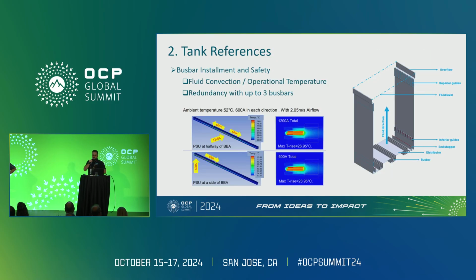Here you have more examples, for example the fluid convection, how the temperatures are being studied for the busbars. You'll see later on with Kevin when he speaks and touches on the more specific power side of things. But the advantage of the busbars in immersion by itself is that we can take way more of them. So if a busbar is designed to handle 150 amps, for example, we can take at minimum double that in an immersion tank, because it's actually installed at the bottom of the tank, which is typically the part that's better cooled, where the fluid is colder, and from where we can deliver the most.